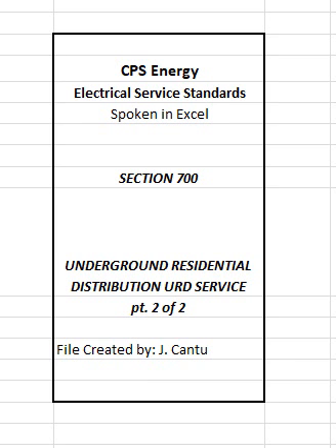704 Clearance from swimming pools. Swimming or wading pools and any associated auxiliary equipment shall not be placed within a 5-foot radius of service laterals. Measurements from the pool will be taken from its inside edge. Swimming pool contractors are therefore advised to have all utilities located before excavation begins.